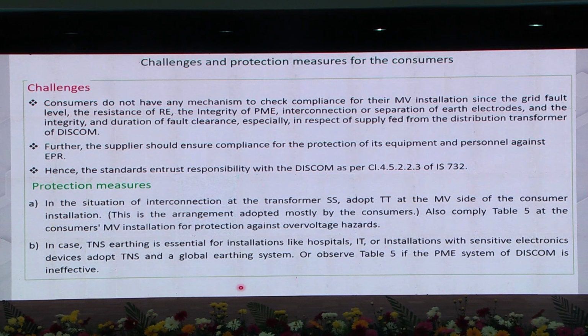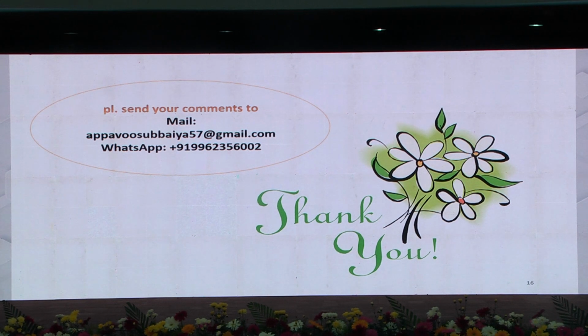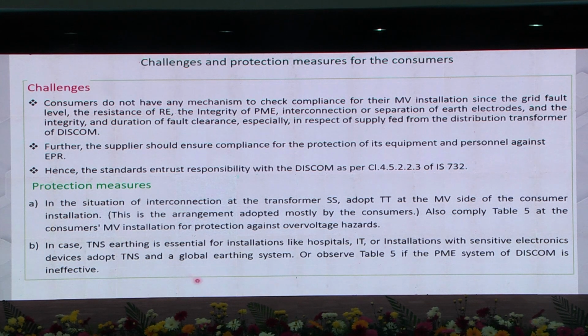The problem is the protection. When the transformer is yours, you can dictate. You can have your own global earthing system, one more protection on the HT side, LT side, etc. But if it happens to be an LT installation, a distribution transformer of the supplier, and you are having a small workshop or small computer center or IT center, then you should adopt this TN system and observe table 5. So this is the thing that we people forget: safeguarding ourselves, and where the neutral is connected, whether it is to be connected with the body or isolated.